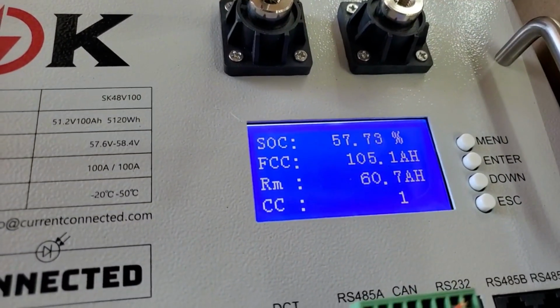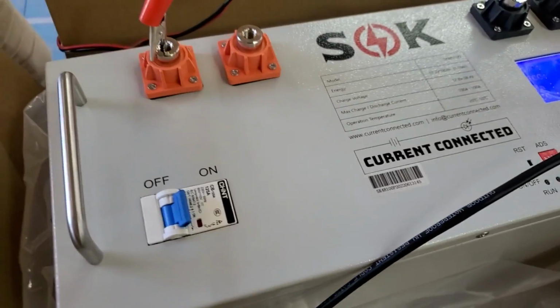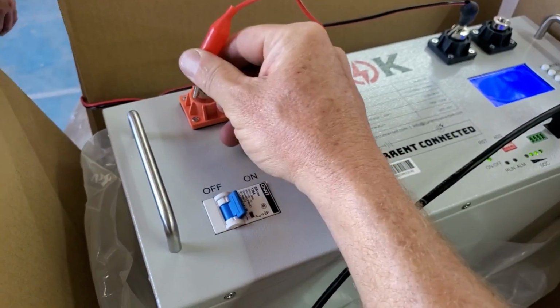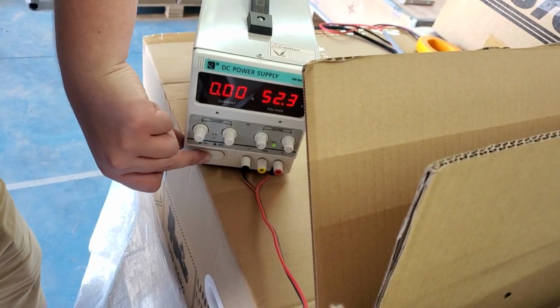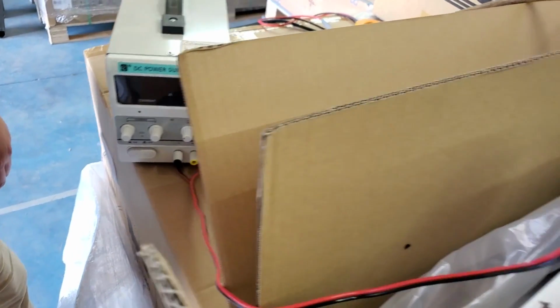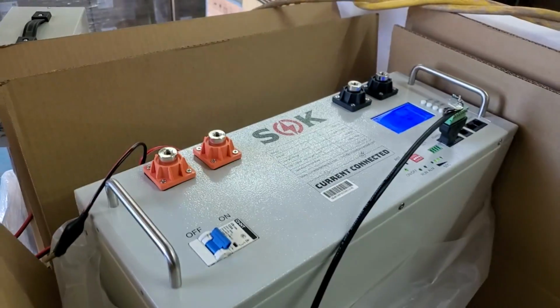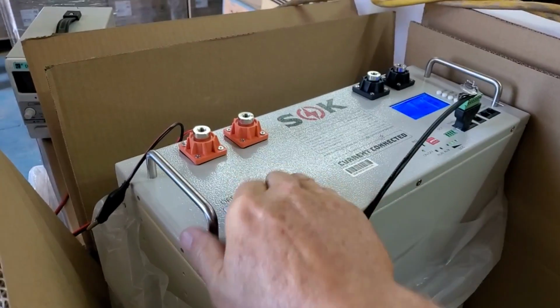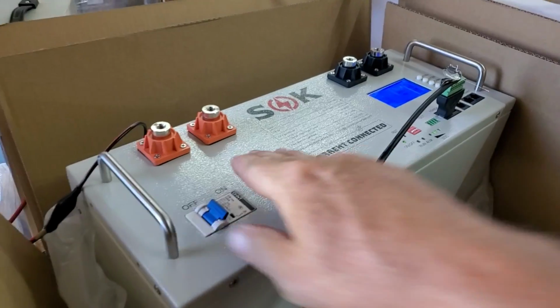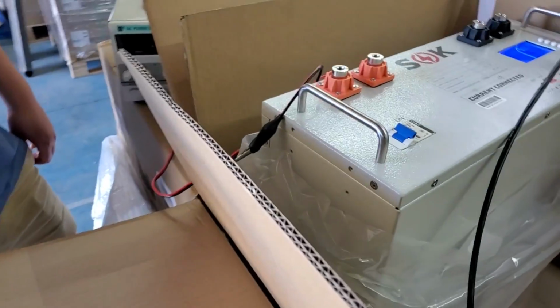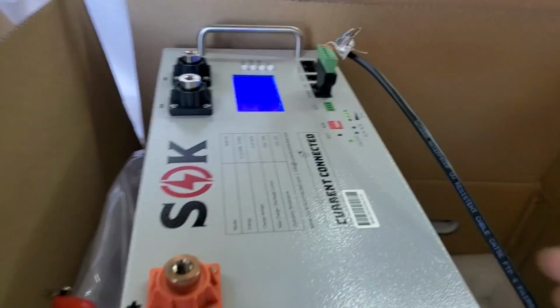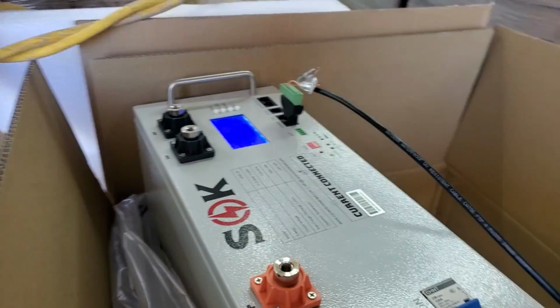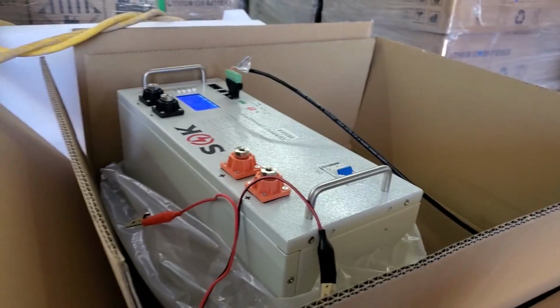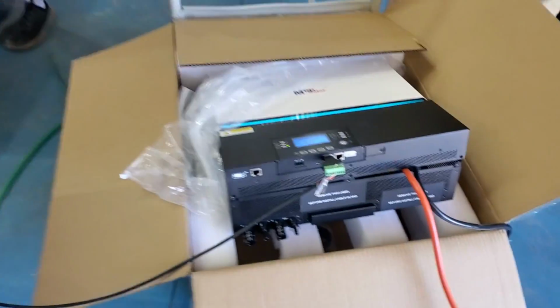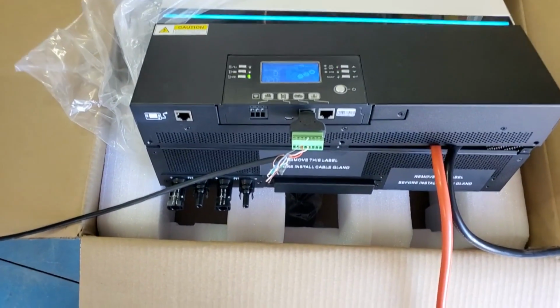It's at 57.73%. So now we can switch our power supply off because the battery's awake — that's why it's good to have a little power supply handy to wake your battery up. This battery is completely standalone; we can switch it off and turn it on again. Now on our inverter we're using the same cable pinouts as with the Pytes battery: pins 1 and 2 on the battery go to pins 3 and 5 on the inverter respectively.